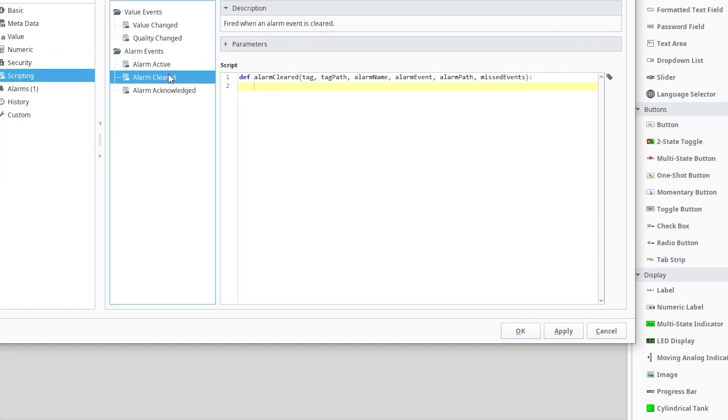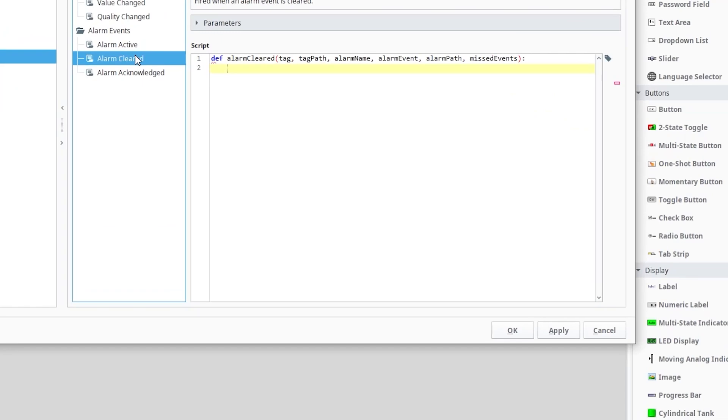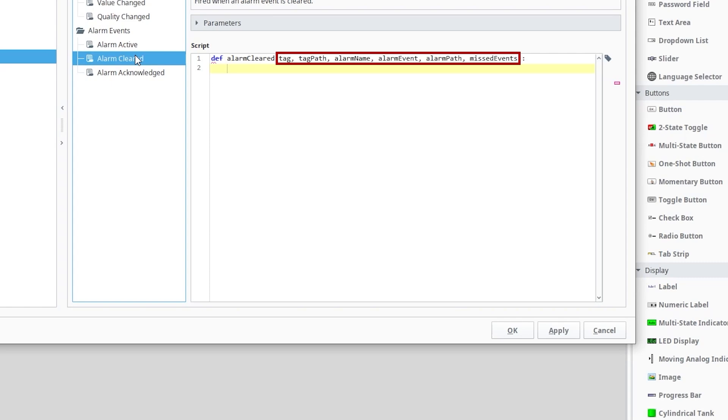The alarm-cleared function comes with a number of arguments that we'll see across many of the alarm events. We have the full path to the tag that triggers the alarm, the alarm's name, an object alarm event that provides many alarm properties, the full path to the alarm, and a missed events flag that indicates when events have been skipped due to an event overflow. There is also this tag argument that gets used in every tag event, not just the alarm events.